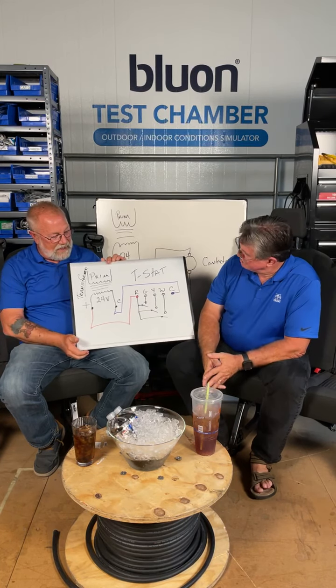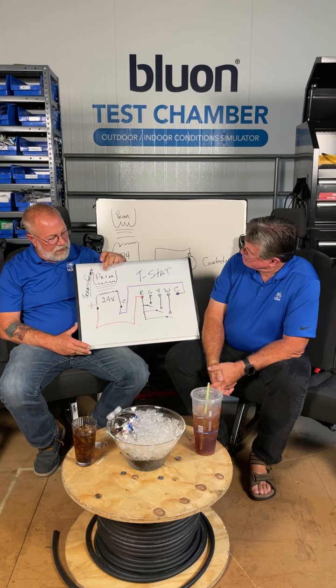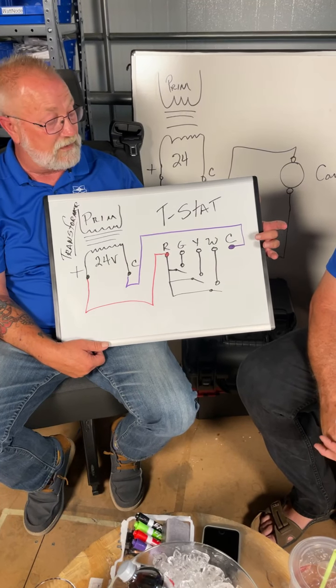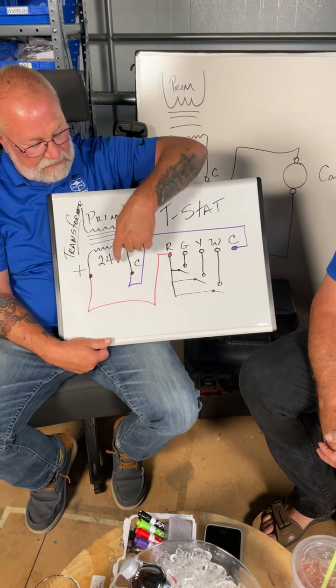So you have a transformer that's primary voltage, and the reason I listed it as primary voltage is it depends on whether you got a 115 volt transformer or a 230 volt transformer as your primary power. So that's primary. Then you have your 24 volt section. If you look at the thermostat, the 24 volts from the transformer goes to R. Now break it down to make it easy for yourself. G is your fan, Y is your cooling, and W is your heat. You notice there's no switch for C on the thermostat. If it calls for C, which most of the digital programmable thermostats do, C comes back to the transformer.